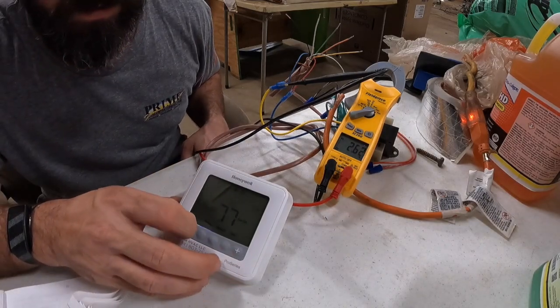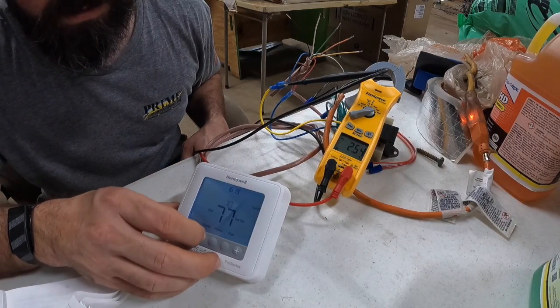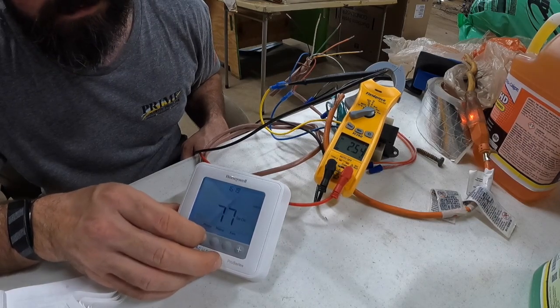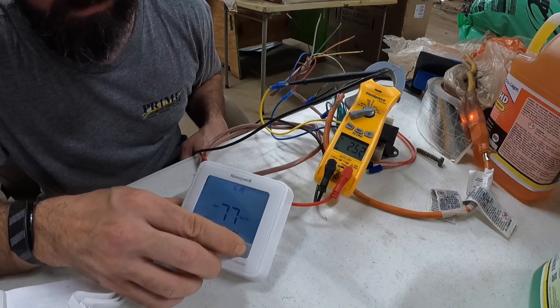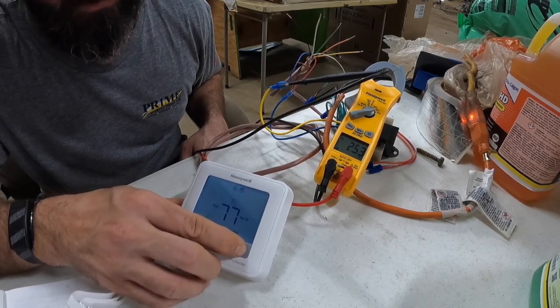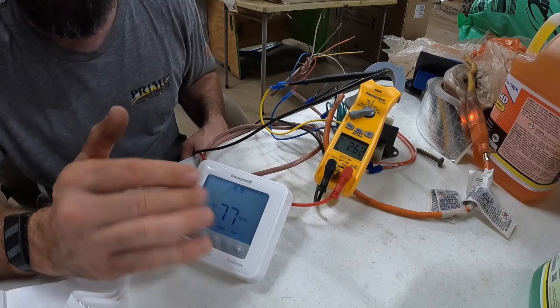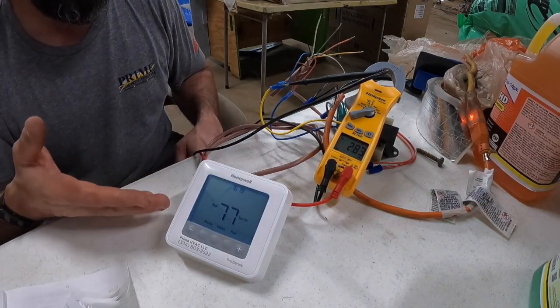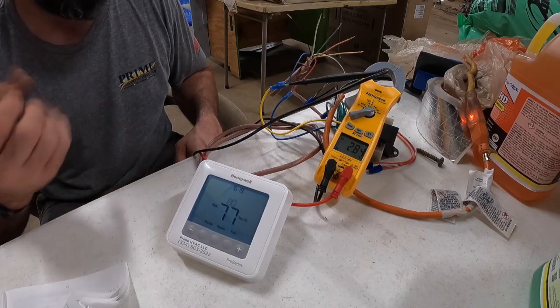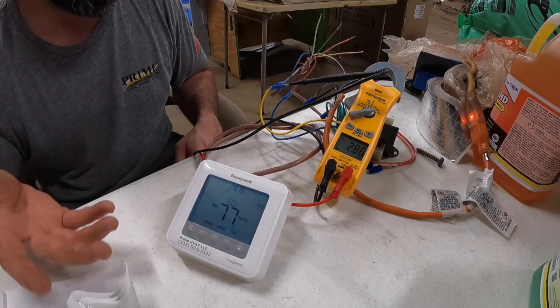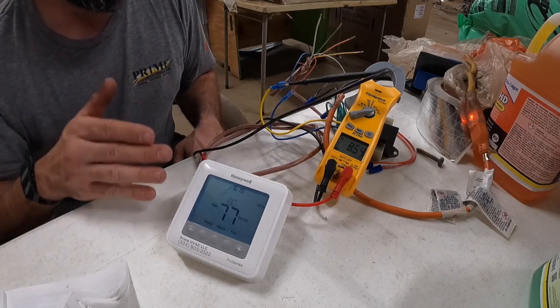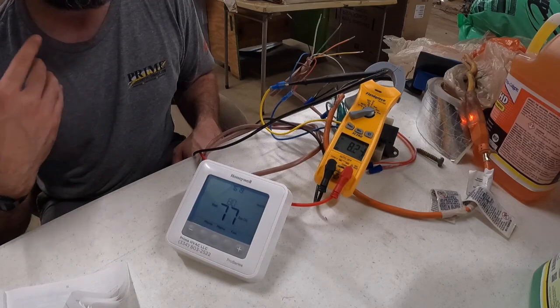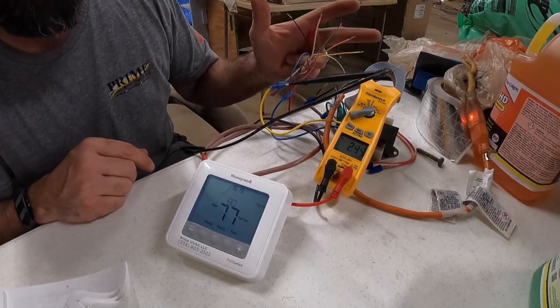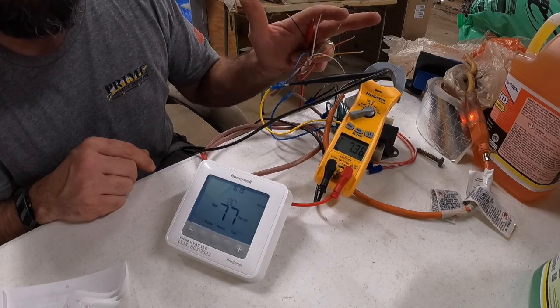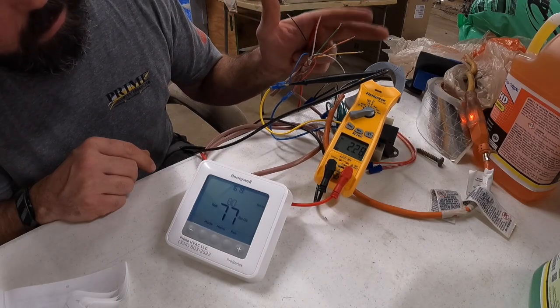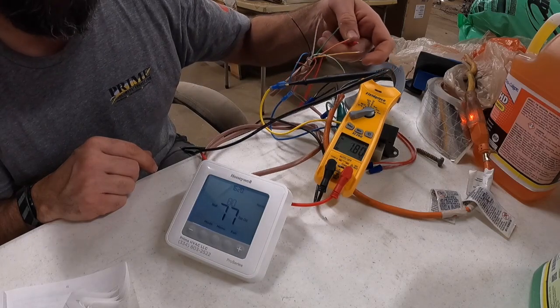All right, so now let's go to regular heat. And we've got to bring the temperature up. This thermostat also has a 5-minute compressor protection delay on it. So I turned that off, I've disabled it, but if you were doing this and it's just flashing cool on, or it's not coming on, it may be in that 5-minute delay. But now that we're calling for heat on a heat pump with an O designation on the reversing valve, Y should be energized, G should be energized, and that's it, until auxiliary heat comes on.